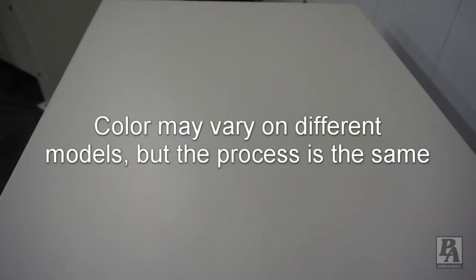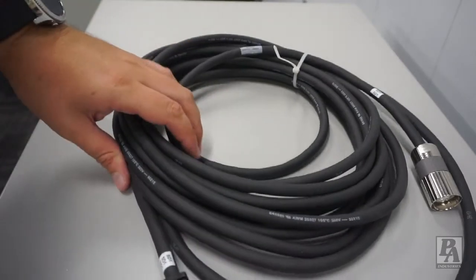Another possible cause could be a defective encoder cable. The encoder cable is the cable connecting the drive to the motor and is what provides the motor feedback. Firstly, we recommend powering down the control and disconnecting the encoder cable at both ends.